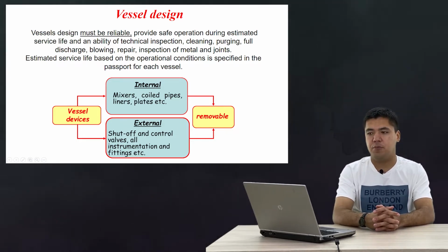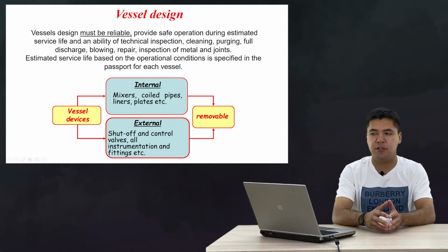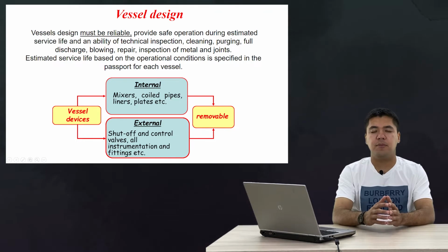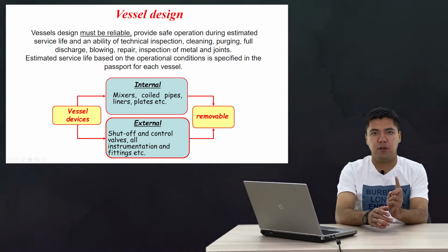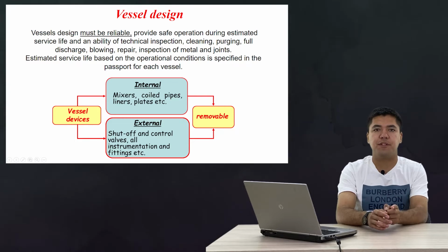And next, pressure vessel design shall provide safe operation during the estimated service life and the ability of technical inspection, cleaning, purging, full discharge, blowing, repair, and inspection of the pressure vessel. The estimated service life of the pressure vessel must be given in the passport of the pressure vessel.